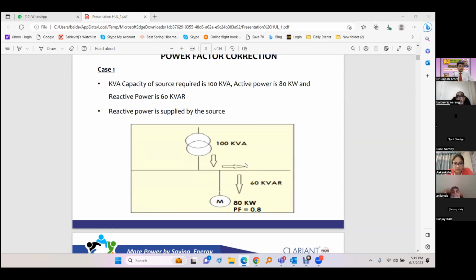So these days there are tariff structures which promote putting reactive power support in the industry itself, at the load itself. The billing is designed in such a way that if you maintain power factor close to unity, you get all the tariff advantage. The billing has now gone to kVAh. So if you maintain unity power factor, your kVAh and kWh are the same, although it never happens in practical cases. But people are always trying to do that, so that the dependence on reactive power imported from the grid is reduced.